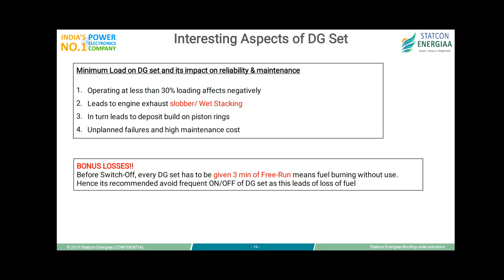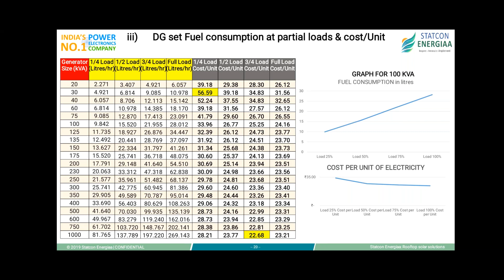Again, when running solar installations with DG sets, we forget that DG set average is a problem. Most of the time, just to justify the whole system, we run the DG at 40-50%, or we curtail the PV power. This is not a very good situation, but we do it just to justify the system.